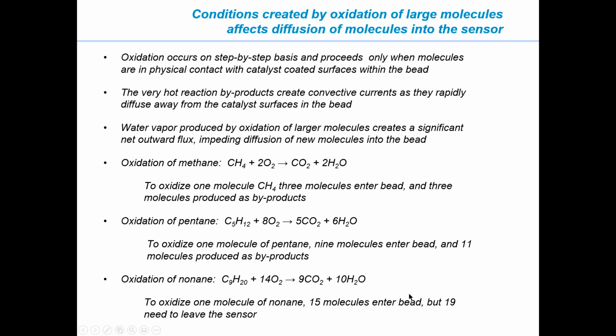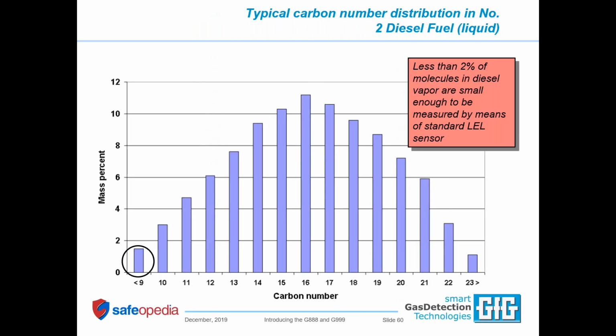And for the whole process, you have 15 molecules that need to enter the bead and 19 molecules that are produced by the oxidation that need to leave the sensor. And each one of these represents a step, and it takes time. And effectively, this is why you don't see the ability of standard LEL sensors operated in the percent LEL range to detect big molecules like the ones that you see in diesel fuel, diesel vapor, in kerosene vapor, in jet fuel vapor.